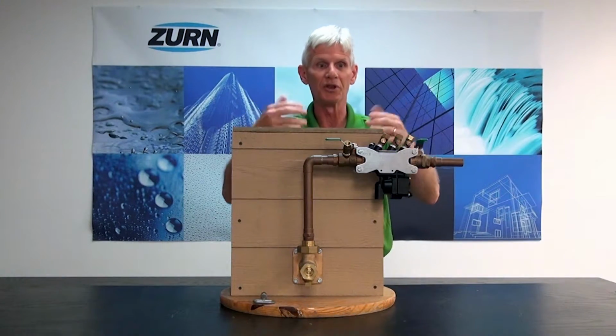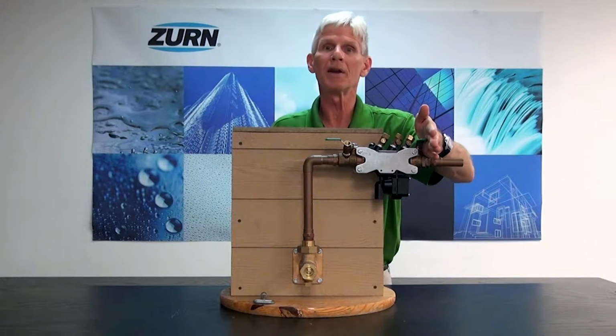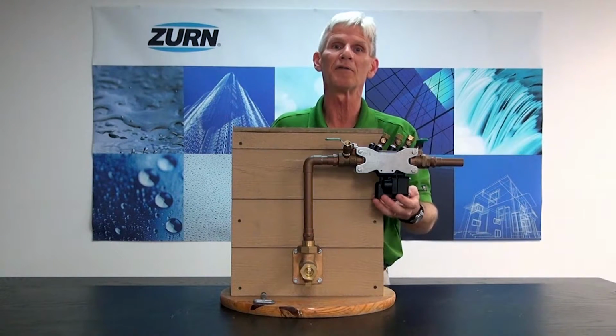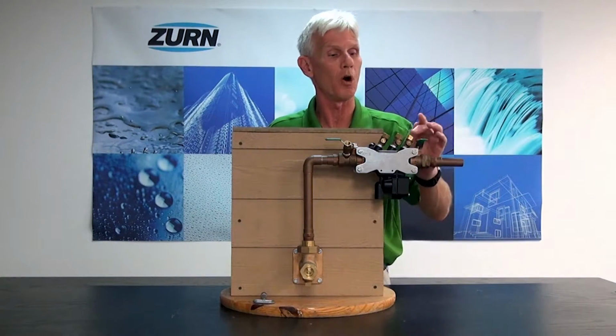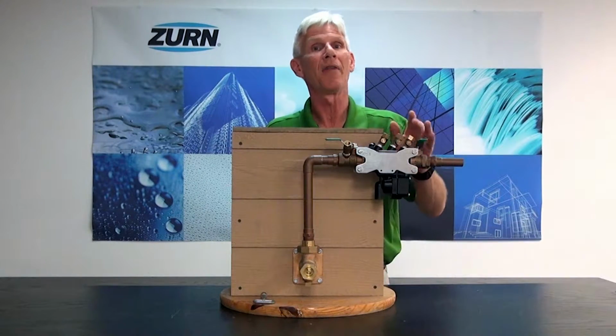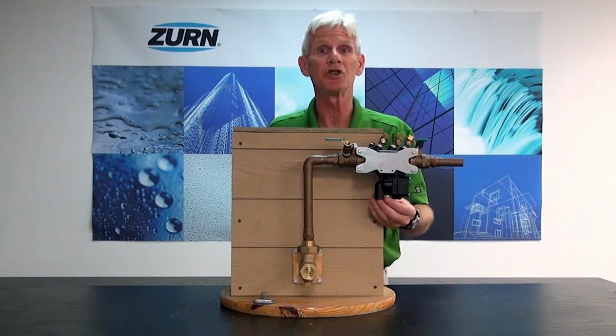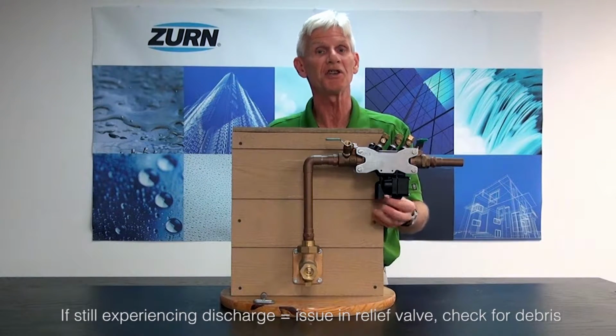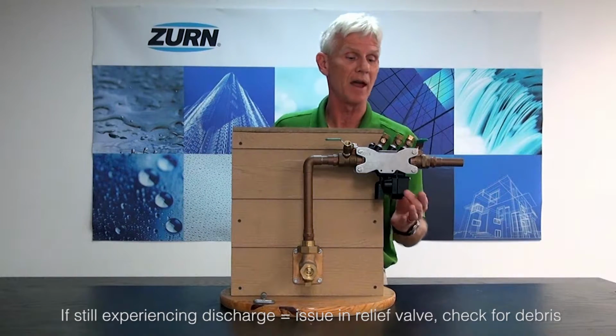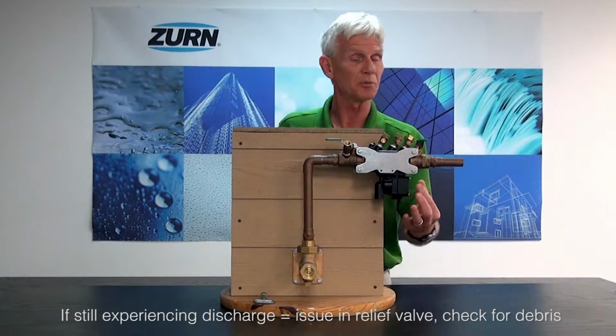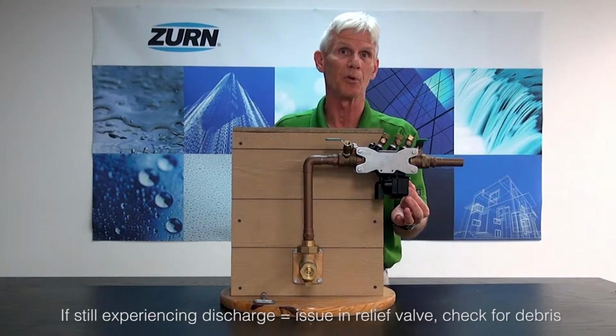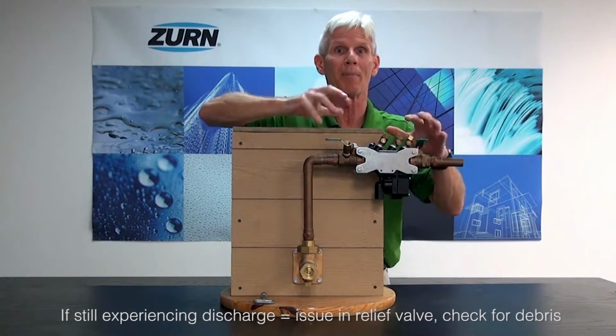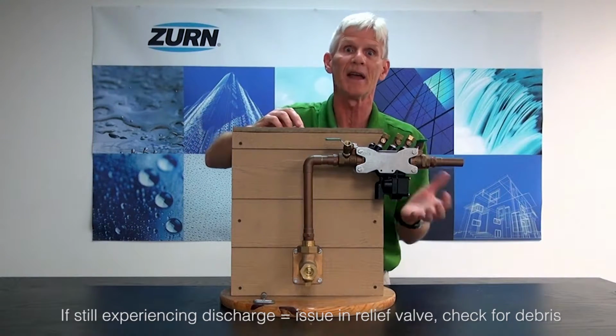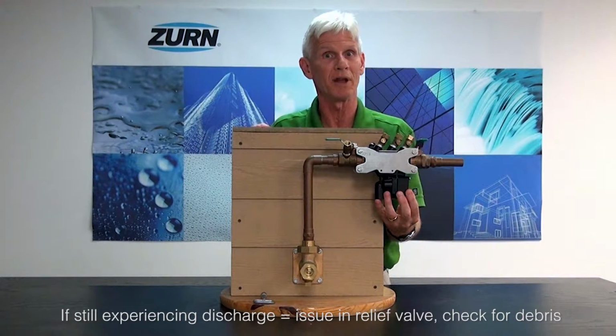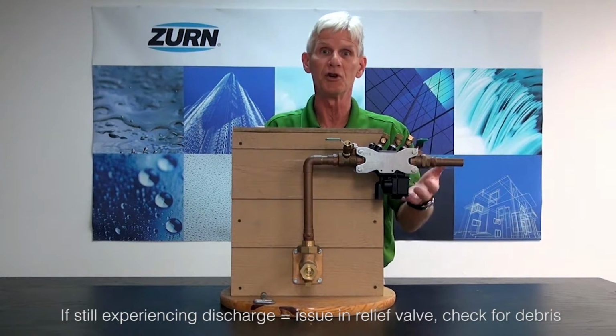Lastly, just going through these steps again, if I've shut off my number 2 shutoff valve and my relief valve discharge doesn't change, I want to open test cock number 4. At that point in time, if my relief valve discharge does not diminish or cease, that tells me that I have a problem in the relief valve proper. That's most likely just the result of fouling with debris. In that case, I'll go ahead and shut my backflow preventer in, relieve the pressure, and again, open up that relief valve and get inside there, clean up the rubber, and do whatever I can to make it stop leaking.